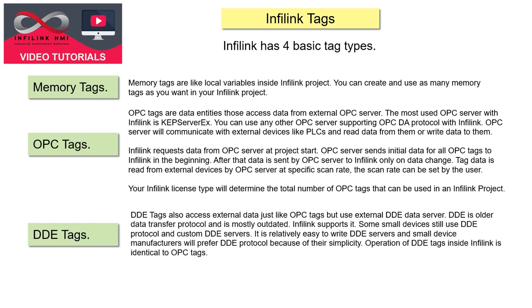DDE tags. DDE tags also access external data just like OPC tags, but use external DDE data server. DDE is older data transfer protocol and is mostly outdated. Infilink supports it. Some small devices still use DDE protocol and custom DDE servers. It is relatively easy to write DDE servers, and small device manufacturers will prefer DDE protocol because of its simplicity. Operation of DDE tags inside Infilink is identical to OPC tags.